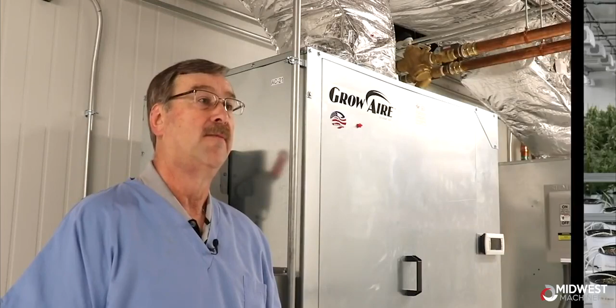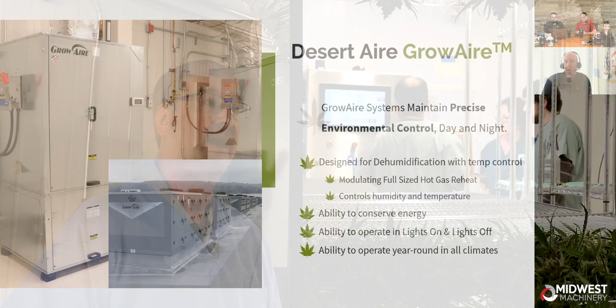The hot gas reheat is using energy that was absorbed through the evaporator coil, both the sensible and the latent, after we've dropped that temperature down to remove the moisture. This is not new energy. This is energy that the customer has already paid for, basically, in the facility, and it negates the need for any type of new energy or additional costs.